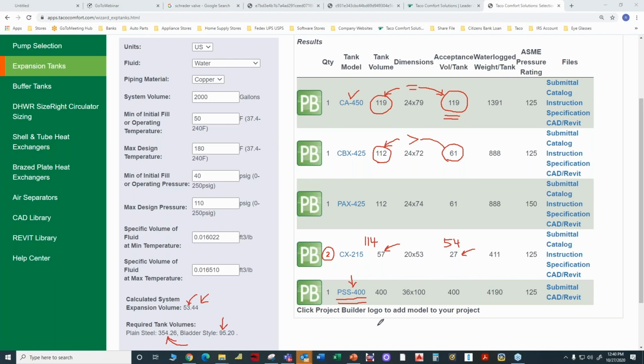No, there's a question. Let me ask this one. I don't know where else to fit it in. If there is a leak in the piping system, will it be seen at the expansion tank pressure gauge, assuming there is no automatic makeup? Yeah, that's an excellent question. So let's assume for a moment that the system temperature has reached equilibrium and there's no more increase or decrease in the system temperature. If the fill valve is closed and there's a leak in the system, yes, the pressure will start going down at the expansion tank. But there's a lot of ifs in there.